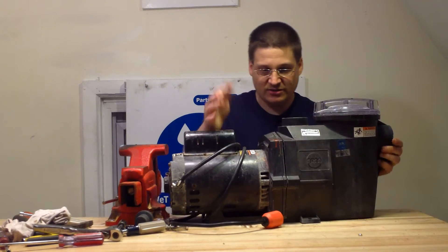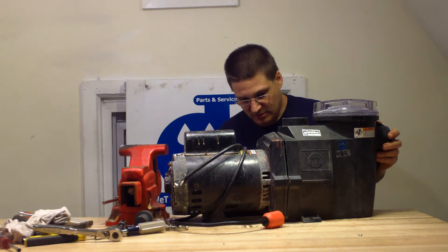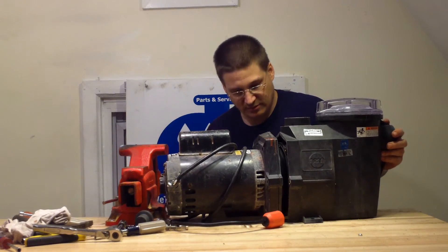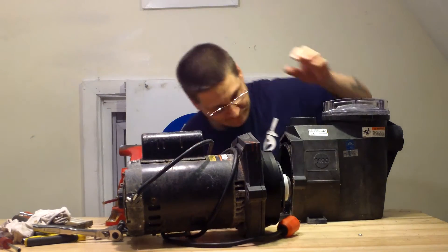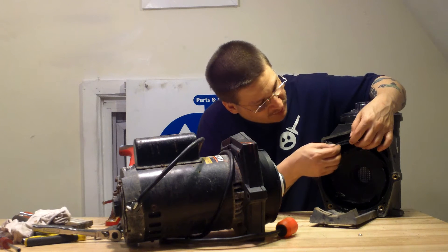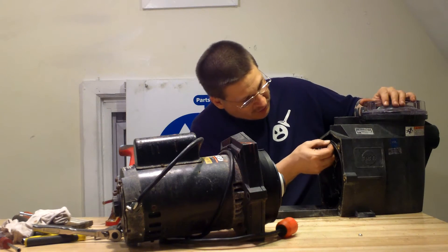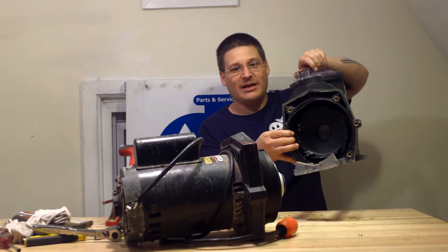Just give this a little tap, just like this. And then we need a screwdriver. We'll pry it apart from the bottom, like so. You want to watch the little seal up in between here. Lift up the motor. Watch you don't damage the inner seal — if you could pop that seal out, you just want to pop it back in here. I'll show you how to put it back in the next video. So that's the wet end — the wet end is removed.